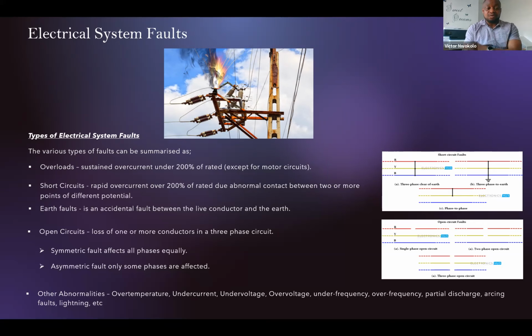So we've got faults like overload, and this is considered a sustained overcurrent under 200% of the rated current, except for motors. And why I say for motors is because sometimes during motor starting, you can have overcurrent exceeding 200%, yet it is classified as overload at that point. So we'll talk more about it. Overload is something that eats up the conductor or the current carrying element of any electrical system, thereby producing heat. So the heating effect is what causes the damage. And we'll look at how to protect against overload in the following slides.